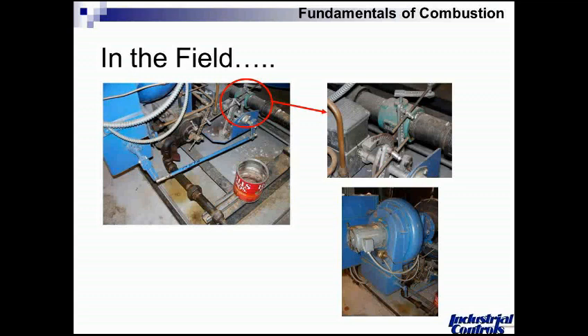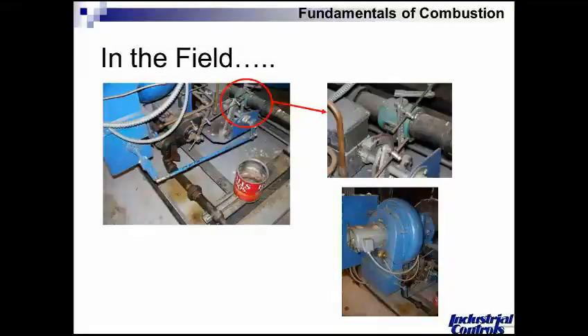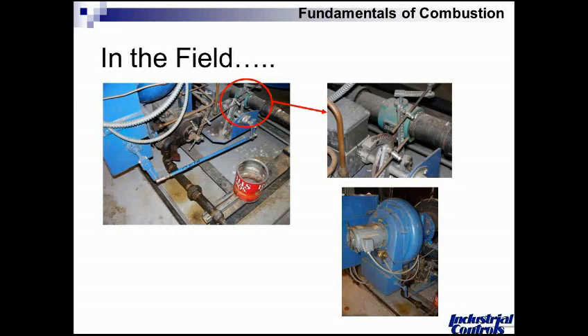As you can even see in the picture on the left-hand side, there is some signs of oxide on the plate. By springs and mechanical force and friction, that's what keeps this whole system working. If someone were to step on this, use it as a step, which we oftentimes see, you're going to start seeing things get bent.